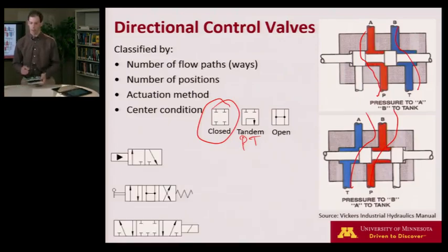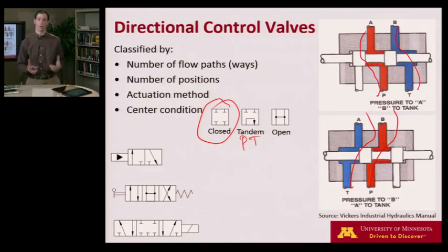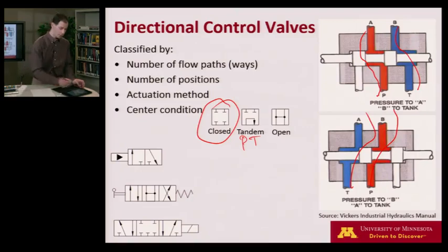I've got three example valves down here. Let me quickly explain how we take these schematics and describe the valve. This first valve would be referred to by its number of flow paths. In this case we have three different flow paths, so this is a three-way valve. I have two shiftable positions, so this is a three-way, two-position valve.